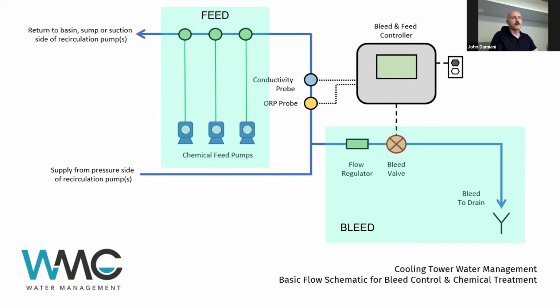Okay, so the chemistry that we add complements the bleed program. So the bleed gets things under control as a baseline, and then we add chemistry on top of that to help protect against things like corrosion, keeping sludge and scale forming precipitates from depositing on surfaces, anything that does form in the system or ends up in the system through air scrubbing. We want to keep that mobile so that it actually leaves through this bleed system. So usually your chemical feed is a single product that combines your scale and corrosion inhibitors, and then you have a two-stage biocide program. So you'd have an oxidizing biocide and then a non-oxidizing biocide. And they operate in a little bit different ways, just to help keep things under control over the long term.